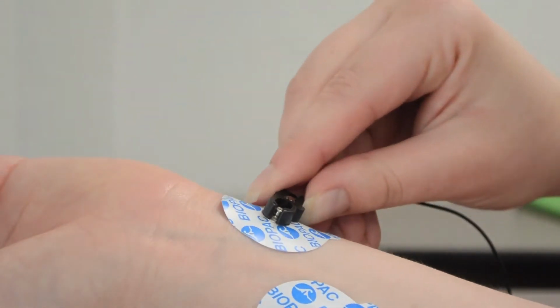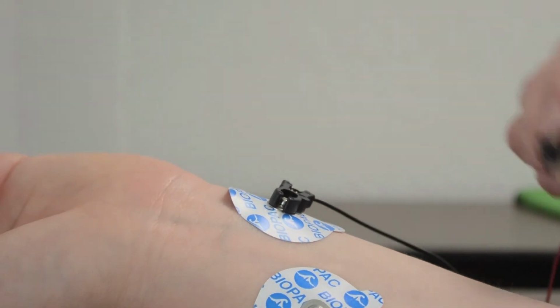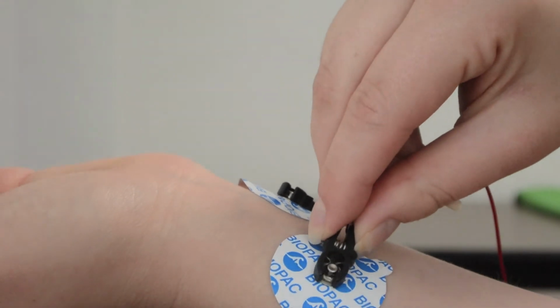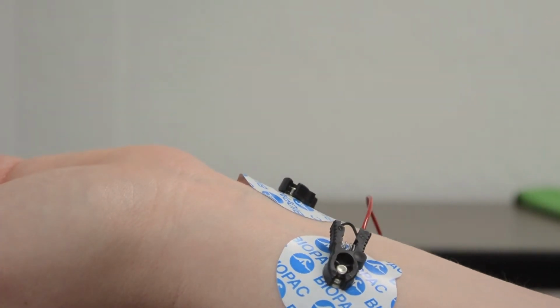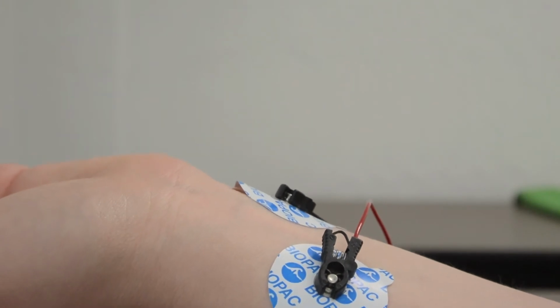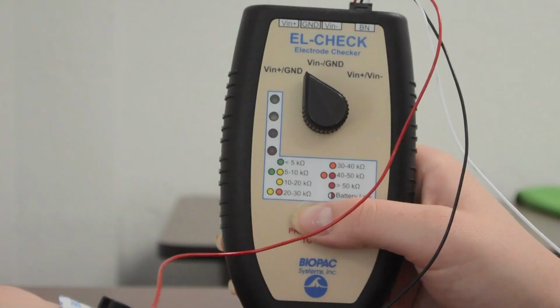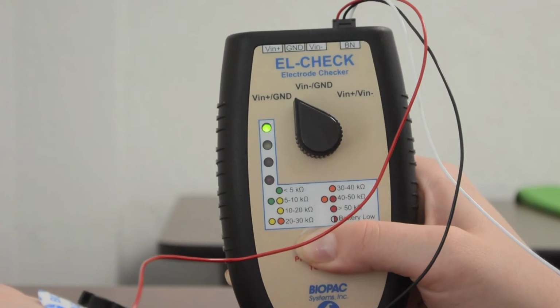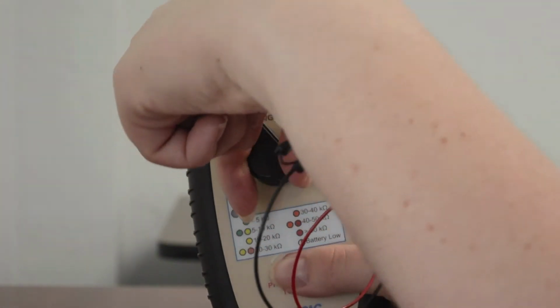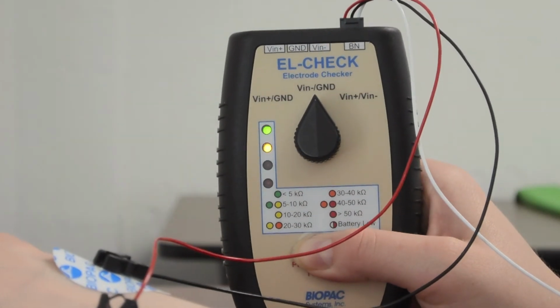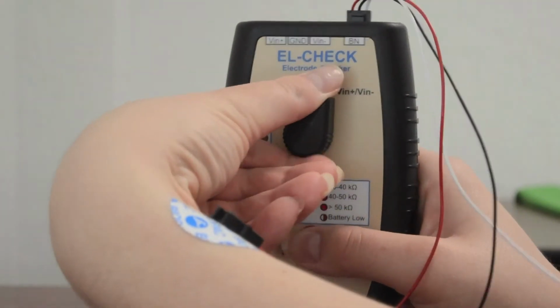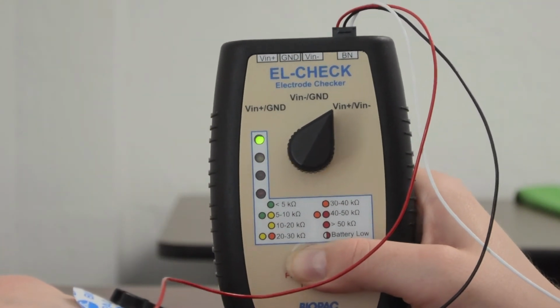Now we'll attach the leads to our participant. Once all of the leads have been attached, we can begin verifying the impedance. First, we'll take a look at the impedance levels between Vin plus and ground. Now, we'll look at Vin minus to ground. And finally, the Vin plus to Vin minus.